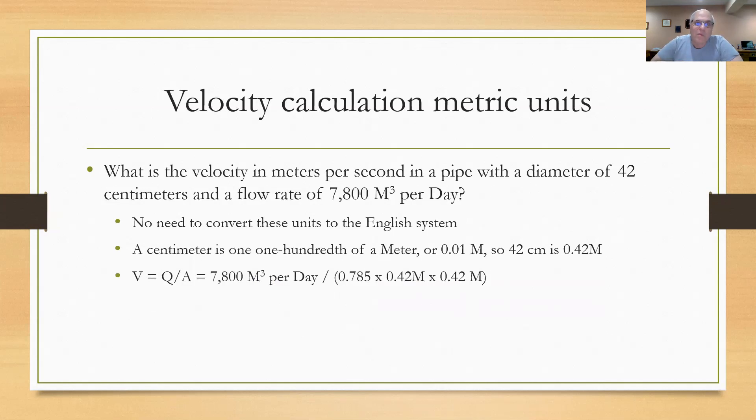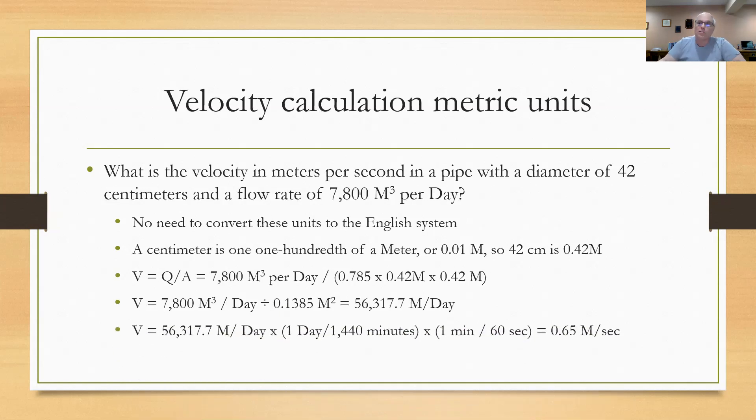V equals Q over A. I've got 7800 cubic meters per day divided by the square area. I calculated the square area by multiplying 0.785 times 0.42 meters times 0.42 meters, which gives me square meters in the bottom. So V equals 7800 cubic meters per day divided by 0.1385 square meters, or 56,317.7 meters per day. If I want that in meters per second, I multiply by one day over 1440 minutes and one minute over 60 seconds. Everything cancels out leaving meters per second and I come up with 0.65.